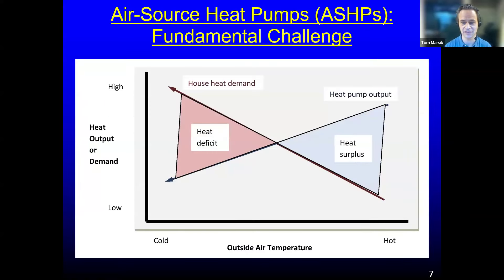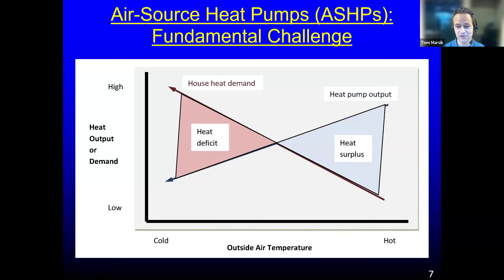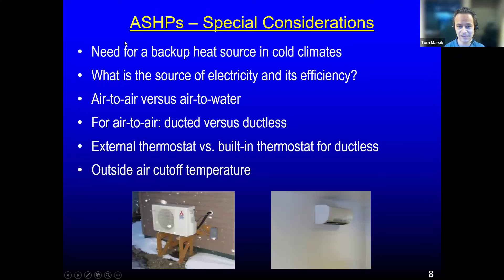There is a fundamental challenge with air source heat pumps: the colder it is outside, the more difficult it is to extract heat from the outside air, so heat output drops as temperatures fall. At the same time, your building's heat demand increases as it gets colder. At some point, if it gets really cold, the heat pump stops working altogether — right when you need the heat source most. That means we need a backup heat source in very cold climates.